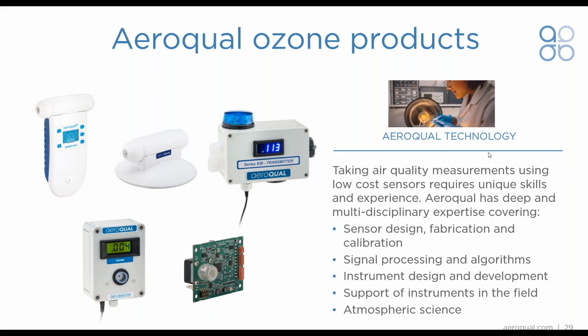You might put this into a workplace or attach it to equipment or to a mobile sterilizing ozone generator, and the same with the Series 930 on the top right-hand side. That's the model that I showed being used, although they don't receive the display or the siren strobe on top, which can be activated if levels get above a predetermined level. So if your control level is set to 0.05 ppm and it hits that limit, your alarm will go off, indicating either that you need to tell employees to move out, or that you might want to check for leaks or something else going on.